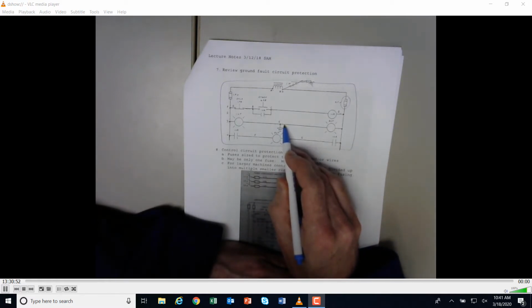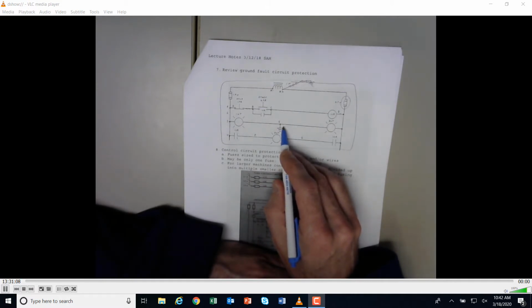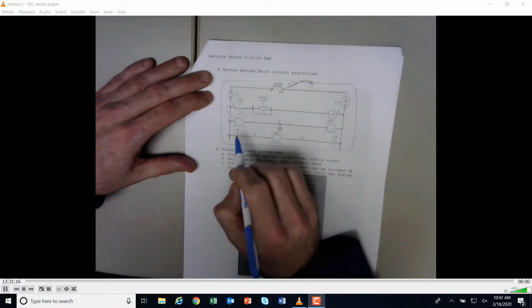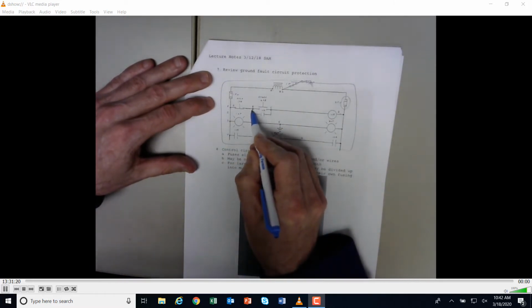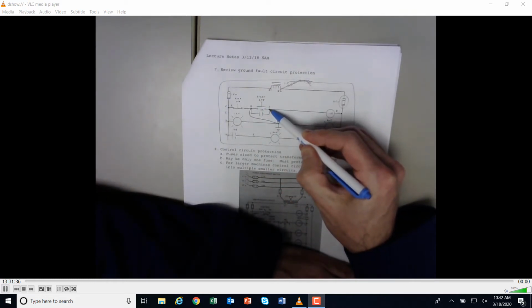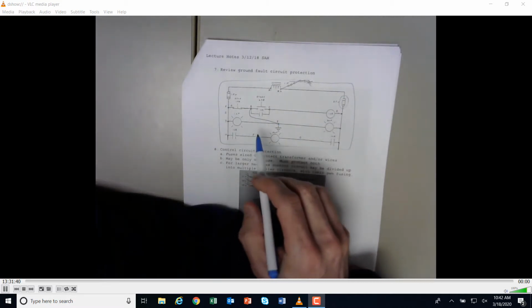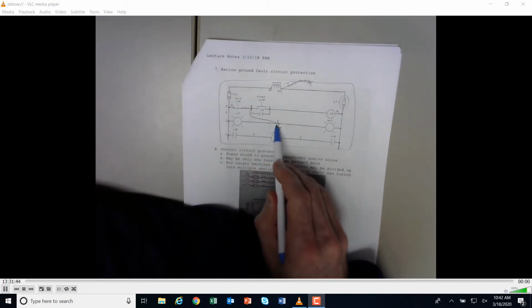And so a similar item, if you're familiar with cars, is that the entire car, the frame, everything is part of the electrical system. So you can bring your current into one side of your device, and then the other side is just the entire system or the entire car. So what this does is, let's say we had a fault here, and this is what you're going to do. If you had a ground fault from, let's say, B, and it was actually touching, it'd be the same as a wire that was brought to this ground, because this represents our system here. If you had something short to the frame, it would be to here, or A or whatever. But let's say we had a short here to E. So what is the flow of electricity? Well, we have a couple of flows of electricity.